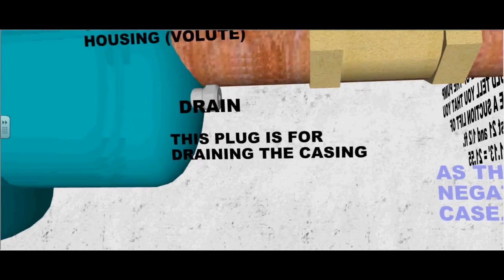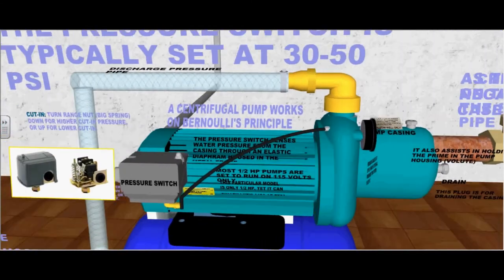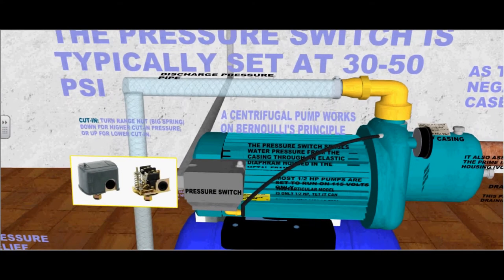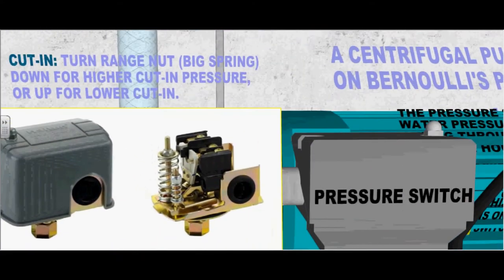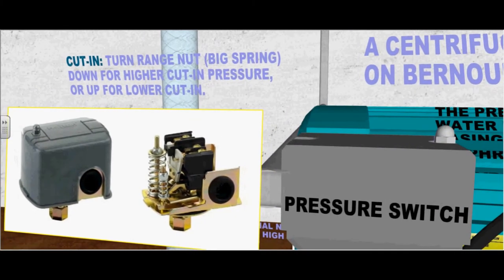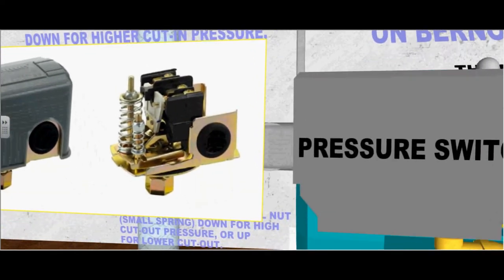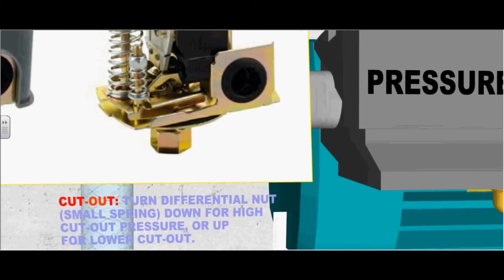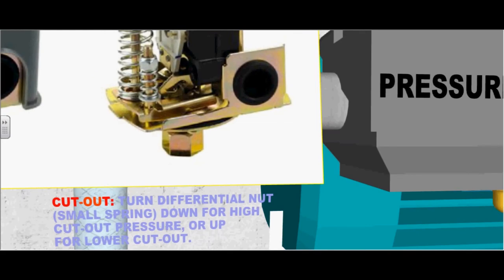This particular drain plug is for draining the casing. This pressure switch is typically set at 30 to 50 psi. Turn the range nut or the big spring down for higher cut-in pressure or up for lower cut-in pressure. Turn the differential nut or small spring down for higher cut-out pressure or up for lower cut-out. This is how you adjust the pressure ranges of the pump.